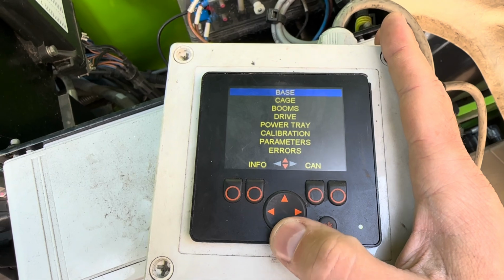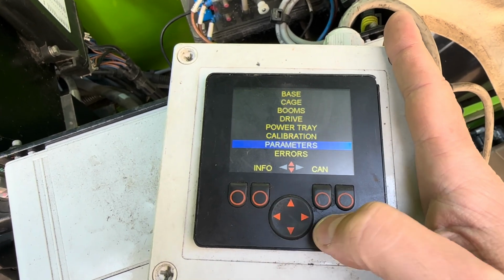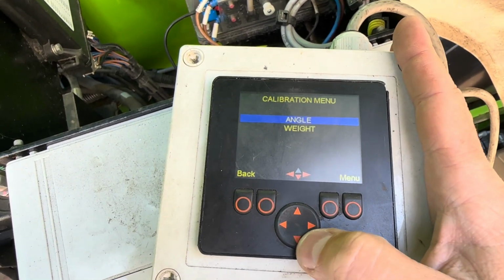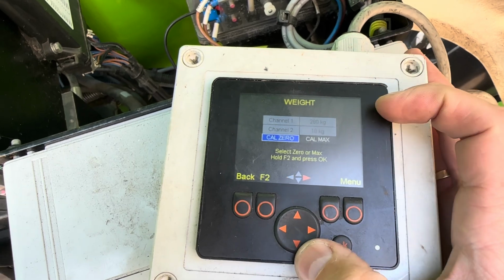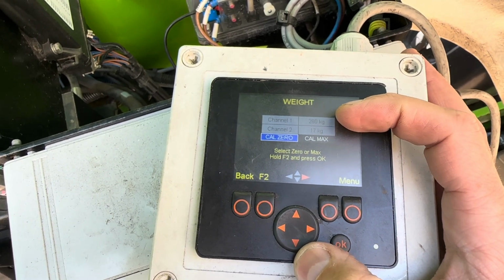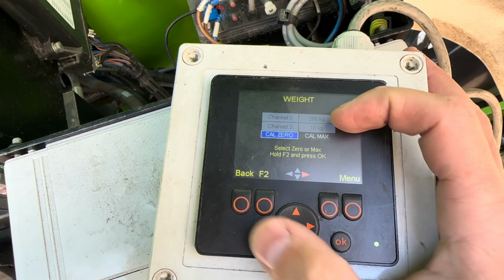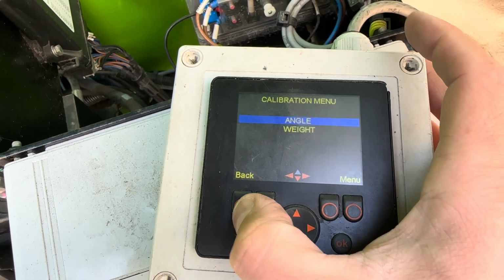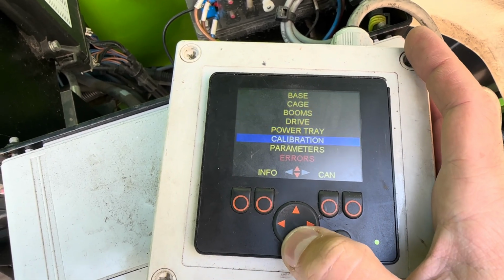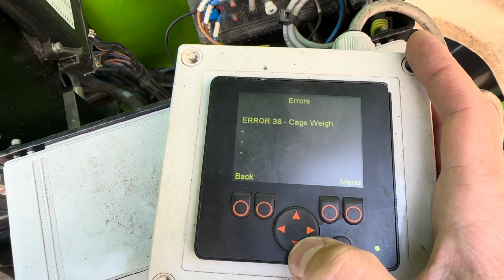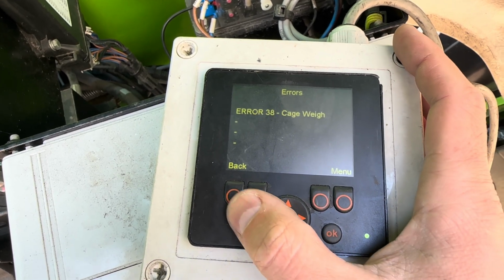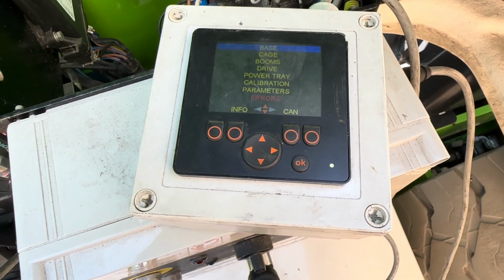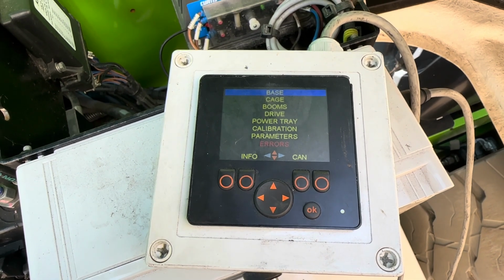So the machine is turning on. You go to calibration, weight. So one channel is completely over 117, and if I go into error codes, it says cage weight error 38. Okay, so that's the issue we have here. I'll try to fix that.